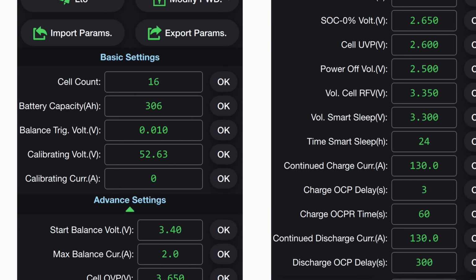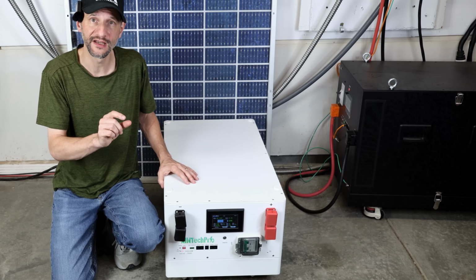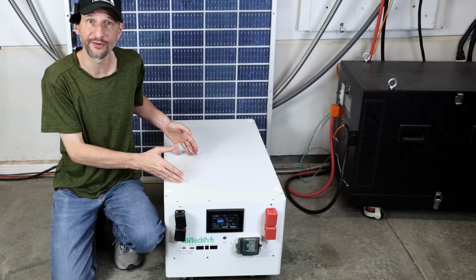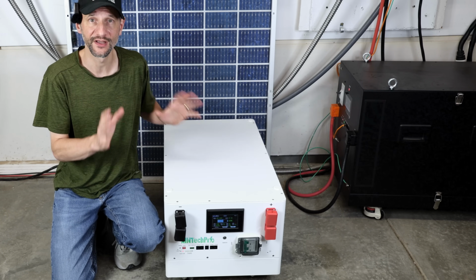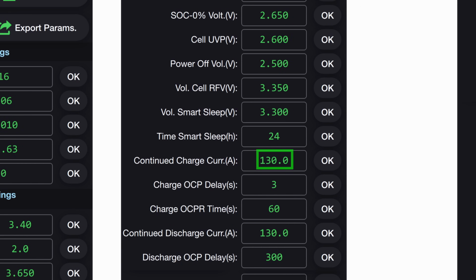If you're using 280 amp hour cells, put in 280. If you're using 314 amp hour cells, put in 314, etc. Second is the continuous charge and discharge current. I am limiting the 200 amp BMS to 130 amps here.